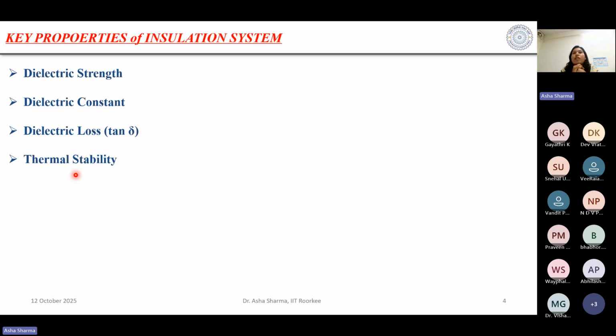The next is thermal stability. What is meant by thermal stability? Let's take the example of the overhead line insulator. Again, it is not perfect; there may be flow of leakage current across the insulator surface in the transmission line. If there is leakage current, there will be I square R losses, and if there are I square R losses, heat is generated. If the heat generated is equal to the heat dissipation, we say this is the condition of thermal stability. But if heat generation is not equal to heat dissipation, there will be thermal instability. So when choosing insulators for my transmission line or power system, I take care of this thermal stability as well.